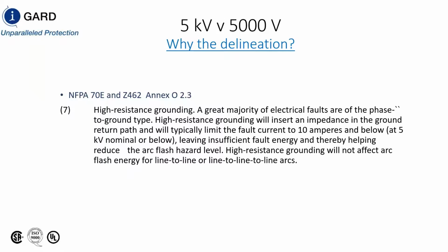So I always stress the delineation between a 5 kV system and a 5,000 volt system. 5 kV is not 5,000 volts. And if we look at NFPA 70E and Z462, specifically Annex O 2.3, it basically says that with high resistance grounding, a great majority of faults are going to be single phase to ground faults. And if you limit the fault current at 5 kV and below, there is insufficient energy to propagate to a phase-to-phase fault. And the issue there is around the 5 kV. I've had this issue with many customers.